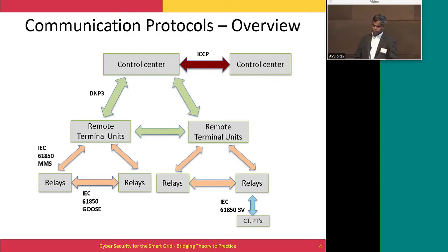From a SCADA infrastructure perspective, as we talked about, there is a control center. Under the control center, a lot of substations are connected. The substations are essentially remote terminal units, RTUs, talking to the control center. That communication is typically DNP3. Within each substation, you have the remote terminal unit talking to relays or other devices, PLCs, or data concentrators and other things. Within the substation, the main protocol used is IEC 61850. It is a suite of protocols. There is MMS, GOOSE. These are some sub-protocols within the IEC 61850 framework.